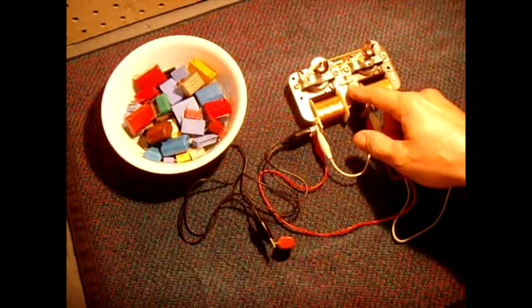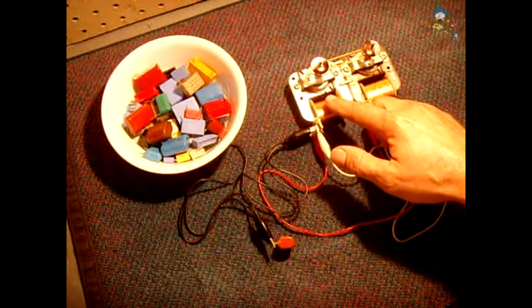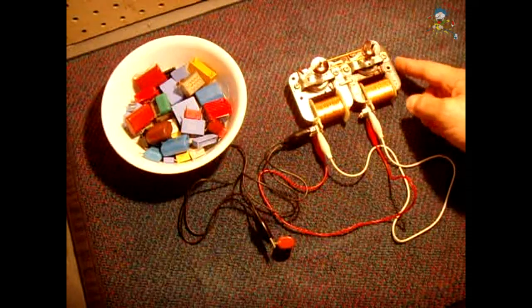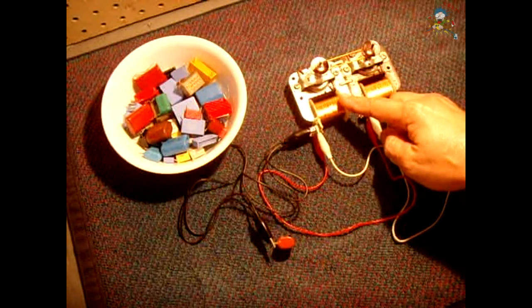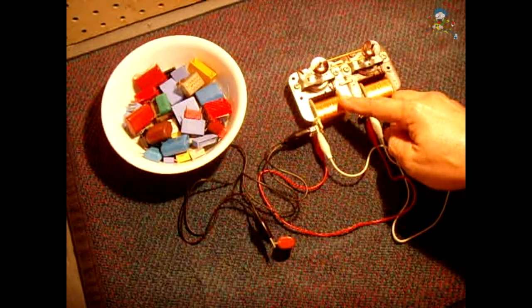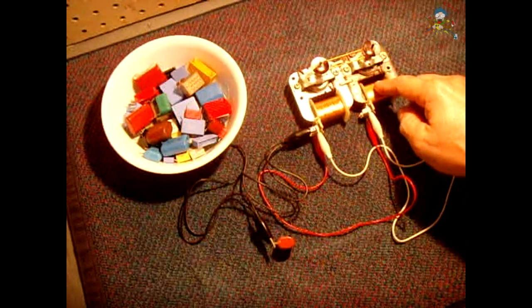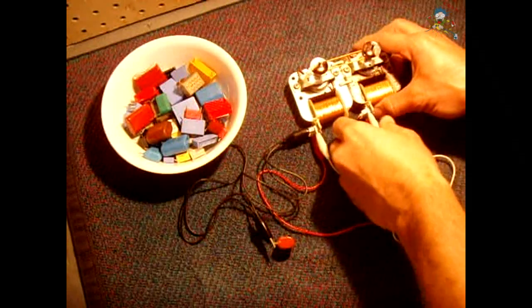In the other video that I saw, it says to use one shaded pole motor which operates at slightly higher voltage than the other. Now in that video, one had 240 volts on the side of it, and the other one said 220 volts. But in that video, which was extremely suspicious, it led me to believe that both motors were exactly the same rating, 220 slash 240. Let me disconnect this, we'll put this back in a minute.